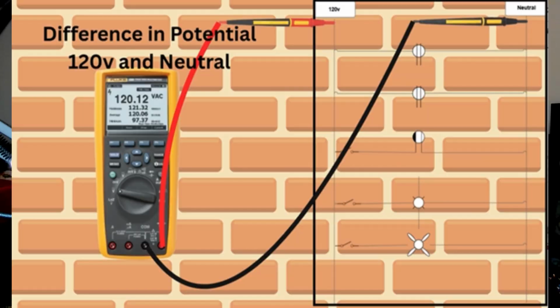You need to see a difference in potential. Either DC, you need to see positive and negative, or with AC, you need 120 volts to a neutral or white wire, 120 volts to another 120 volts which gives you 240, or 120 volts to ground. You need some sort of difference in potential to see it.